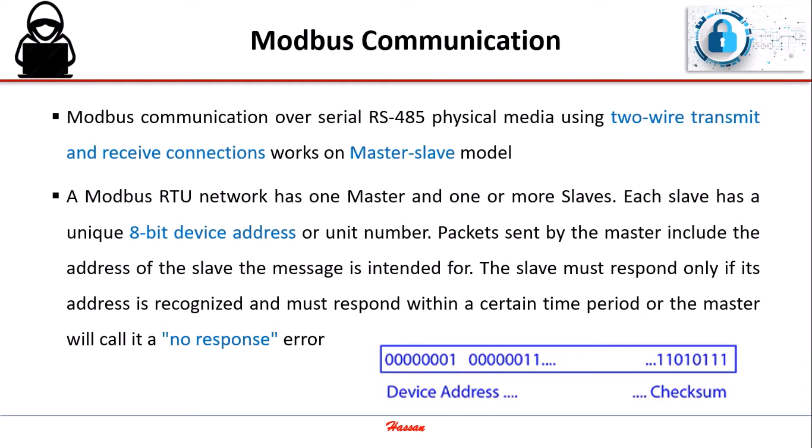Modbus communication over serial RS-485 physical media using two-wire transmit and receive connections works on a master-slave model. A Modbus RTU network has one master and one or more slaves. Each slave has a unique 8-bit device address or unit number. Packets sent by the master include the address of the slave the message is intended for. The slave must respond only if its address is recognized and must respond within a certain time period, or the master will call it a no-response error.